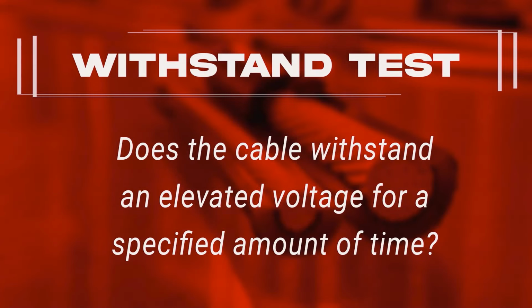The typical medium voltage industrial cable can benefit greatly from just a simple withstand test. A withstand test being, as it sounds, does the cable withstand an elevated voltage for a specified amount of time? Hey Chasen, if I can jump in here.